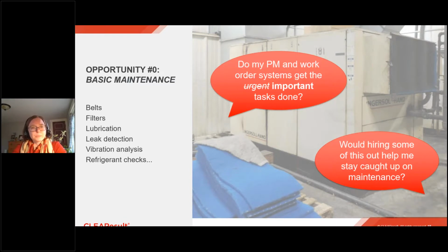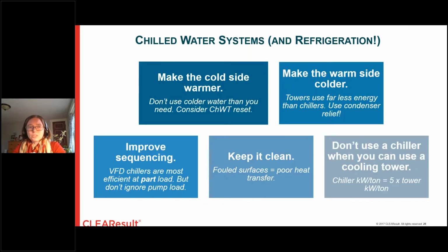So let's move on to our top fives. Chilled water systems and refrigeration was one of our ties for the lead here, so I'm going to throw out a few quick tips here. Chiller power is usually proportional to lift. And lift is the difference between the hot side, so that condenser, and the cold side, which is essentially your chilled water.